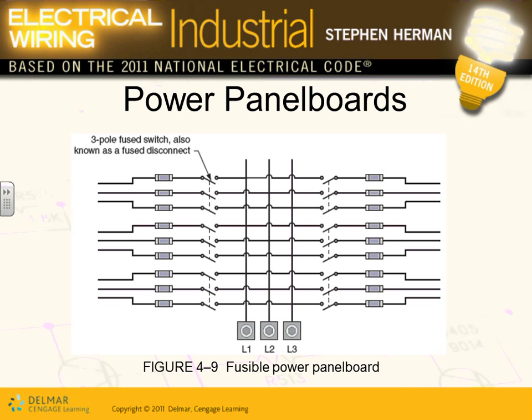Here's what the code says. Very good point. If it's standing like this, A, B, C from left to right. If it's horizontal, top to bottom, A, B, C. If it's standing and you put the buses in front of each other, the depth, the same thing: from the front, looking front, A, B, C. So it goes A, B, C top to bottom, front to back, and left to right. That's the code requirement.